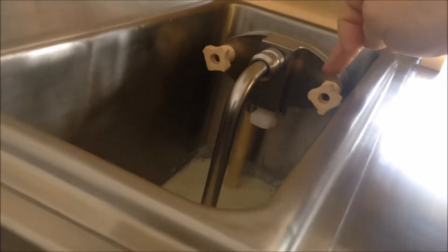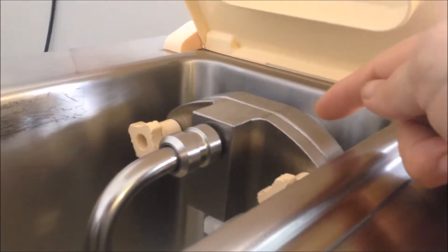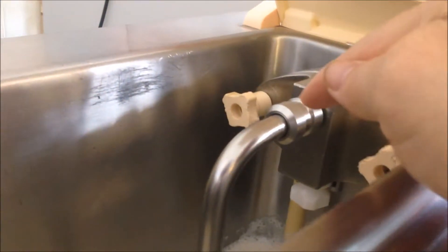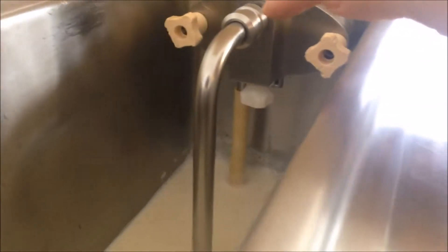On the top we have an integrated plastic cover. Inside we have the pump, which is fixed with two hand knobs — the two knobs hold the front and back parts of the pump together. We have the connector and pipe, and this pipe goes into the hole of the mix hopper. We have the mix in there and the pump draws the mix from there, plus air from the bottom of the pump, and gets the combined mix into the cylinder. It is running now.